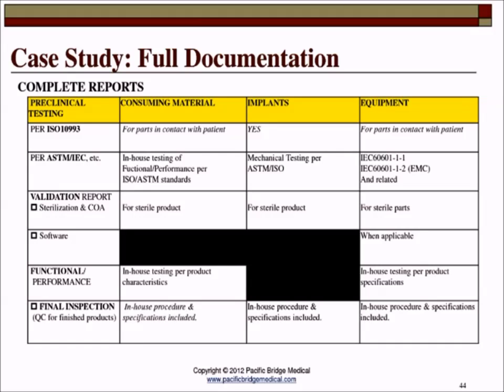Okay, I basically divided the device into three types. The first one is the consuming material, such as dressings, dental materials, or electrodes, etc. And then the implant type. And then the last one is the equipment type. Now, for all the device or any part of the device that is in contact with the patient, biocompatibility testings are required per the ISO 10993 standard. Okay? There are two materials that such testing can be waived. They are titanium and stainless steel.